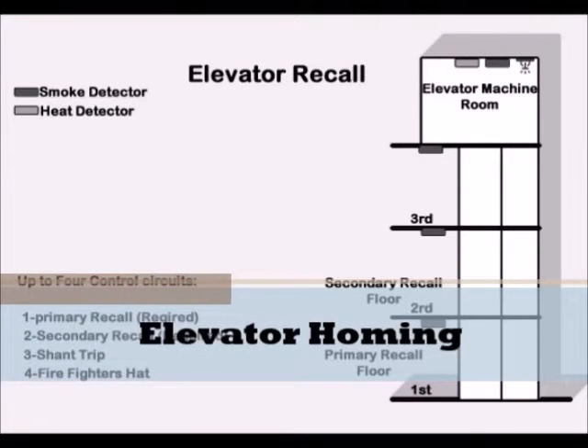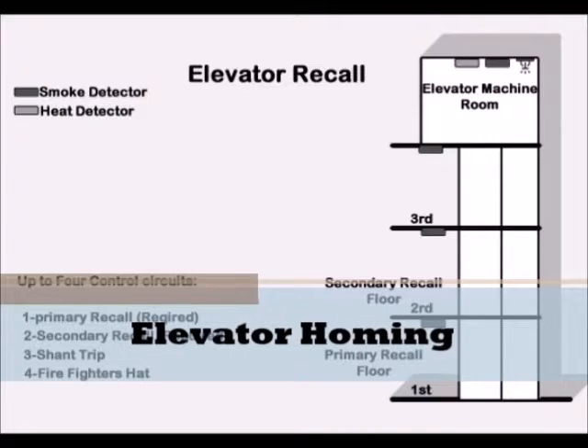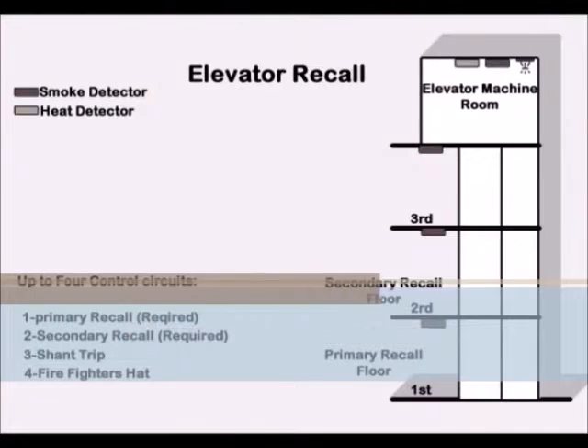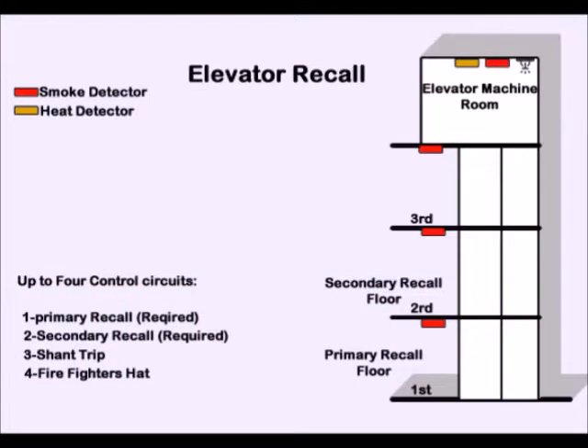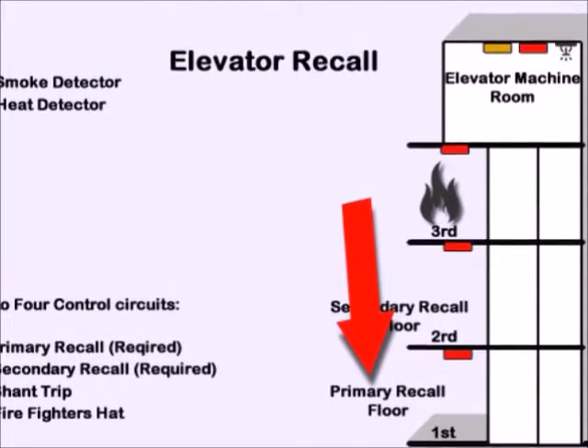Elevator recall refers to homing the elevators when the smoke detectors in the elevator lobbies are active. Usually, the primary floor of homing is the first floor or ground floor. Each elevator lobby typically has a smoke detector. The elevator machine room is sprinkled and has both a heat detector and smoke detector installed. When there is smoke on the second, third, or any floor above that, elevators home to the primary floor, which is usually the first floor.